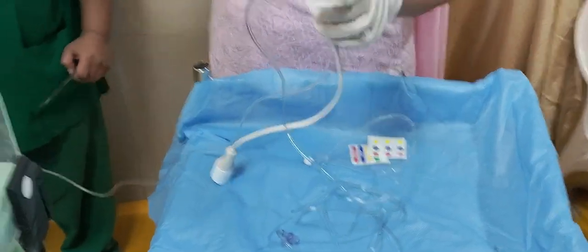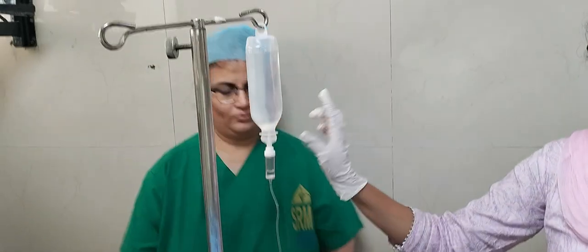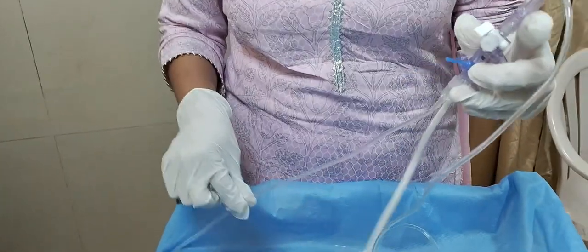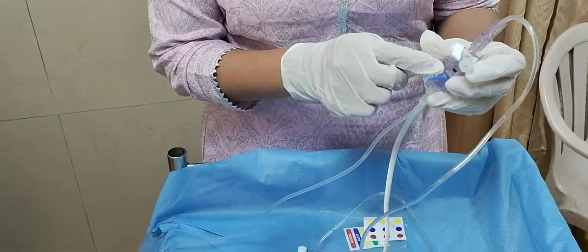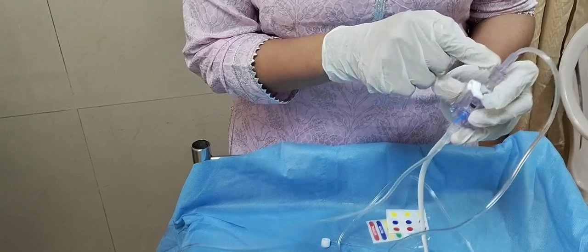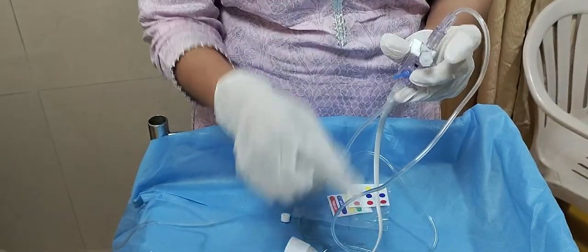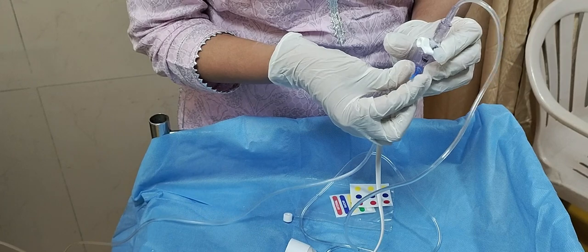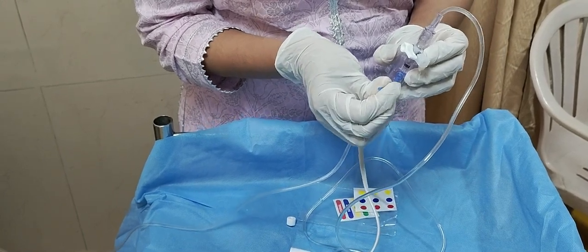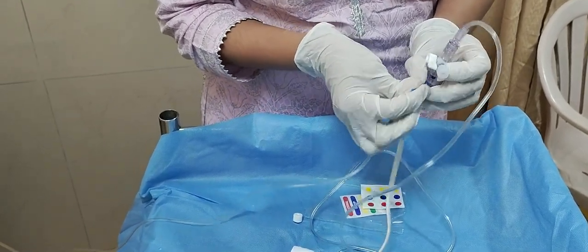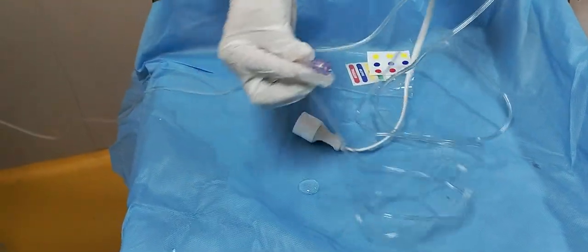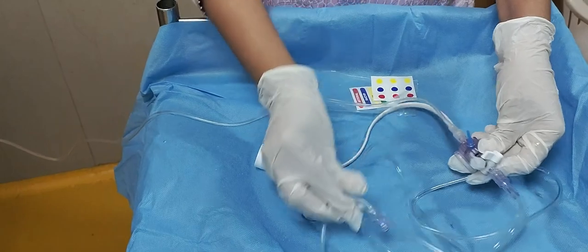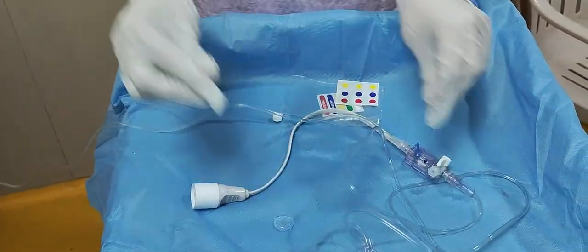So now we are going to flush. I have connected this to the NS. So this is open, the cable is open. So from the NS, the solution comes through this. It has to traverse through the pressure transducer system to this high pressure tubing. That can happen only if I am stretching this. So this entire line got flushed. So all these things have to be handled sterile.